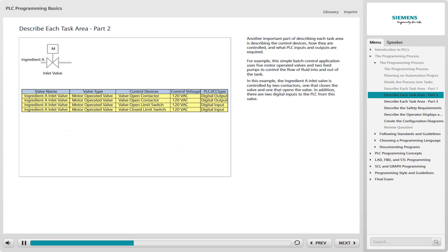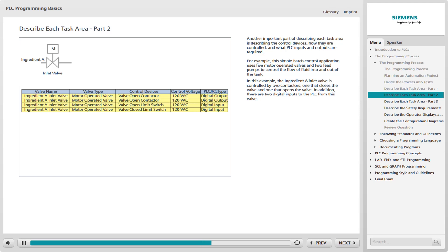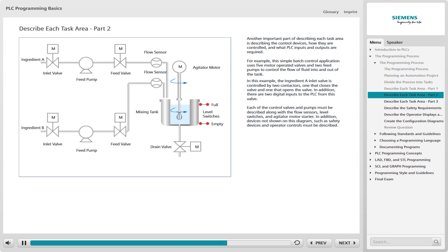In this example, the Ingredient A inlet valve is controlled by two contactors, one that closes the valve and one that opens the valve. Each contactor requires a 120 volts AC signal from a PLC digital output. In addition, there are two 120 volts AC digital inputs to the PLC from this valve, one from a limit switch that signals that the valve is open, and one from a limit switch that signals that the valve is closed.